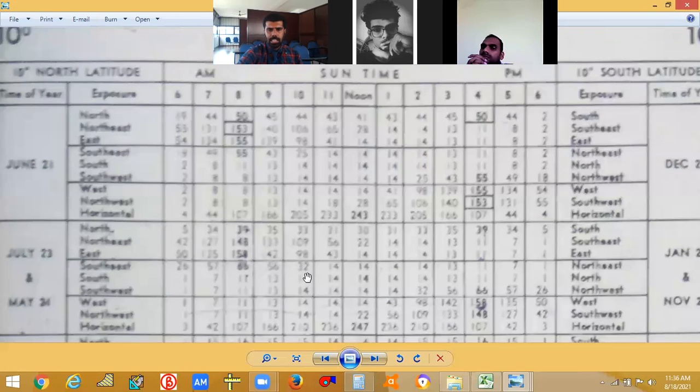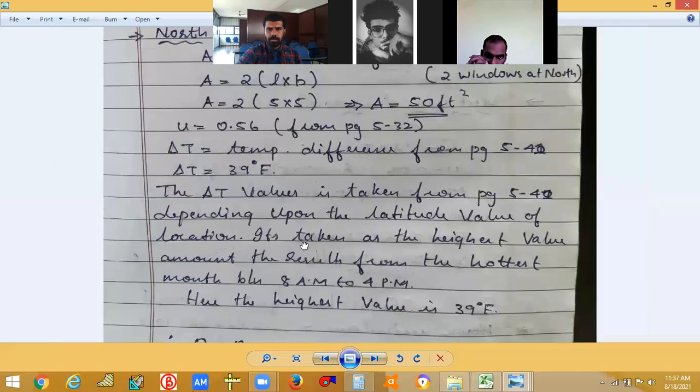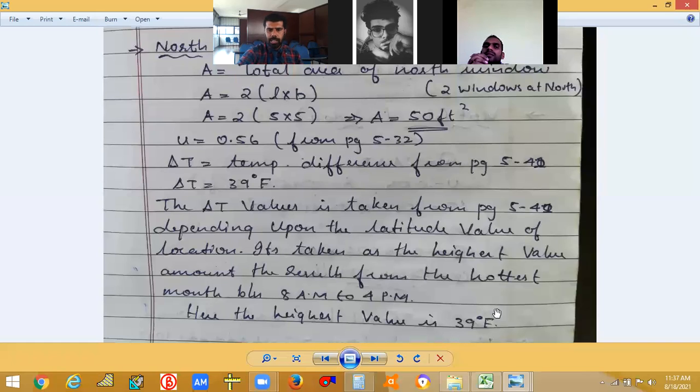Let's see what is the highest value. 39, 35, 33, 31, 30, 31, 33, 35, 39. So what is the highest value between 8 AM and 4 PM in the month of July to May? The north orientation, this 39 degree Fahrenheit. Correct? This 39 degree Fahrenheit. So apply there 39 degree Fahrenheit. So you write how you got this 39 degree Fahrenheit.